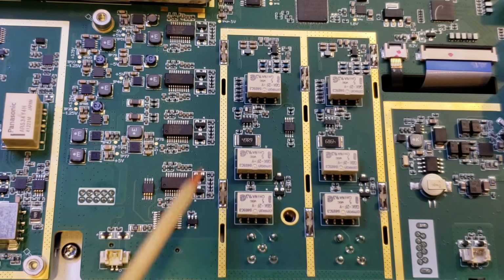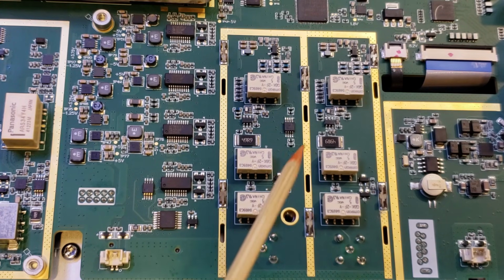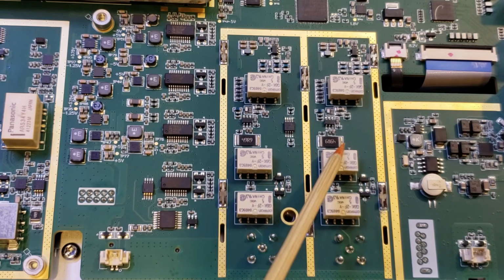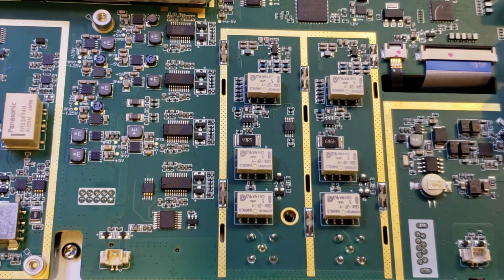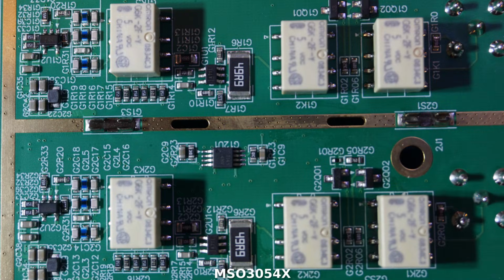And here are our two function generator output channels. You can see the 49.9 ohm resistors here again, and these are for the 50 ohm output impedance. The function generator output portion of the circuitry looks pretty much identical to what's in the MSO3000X series, which is not surprising as the specs are quite similar.